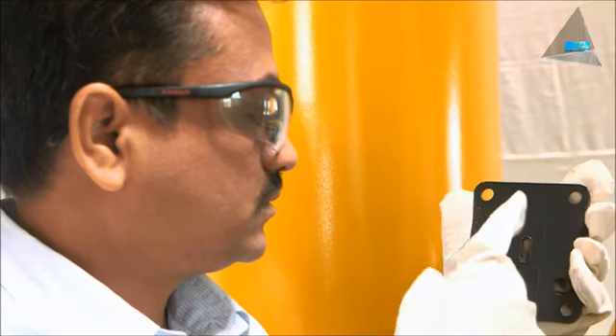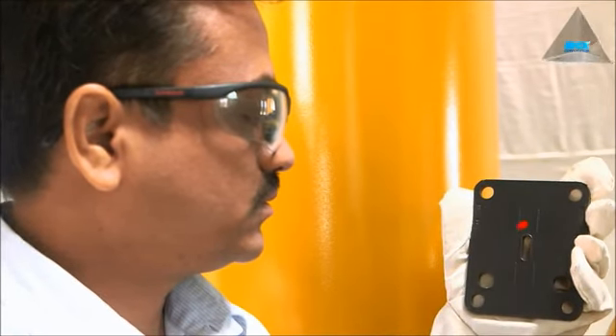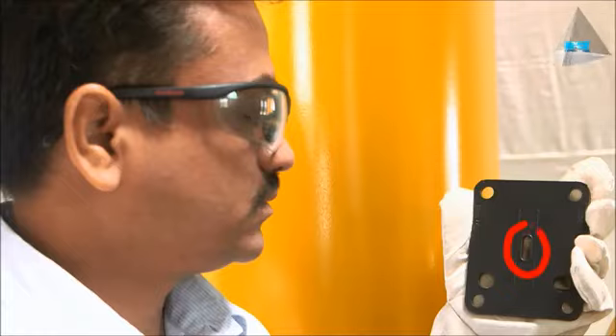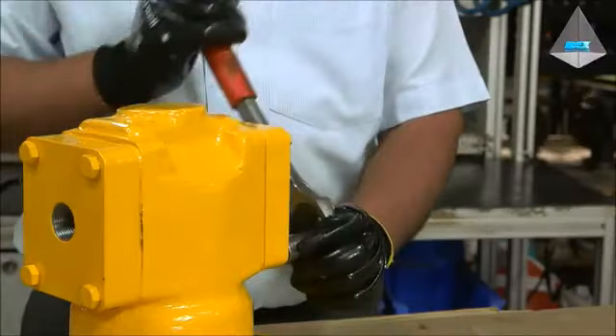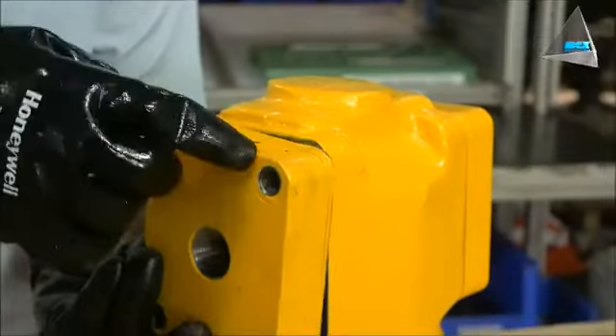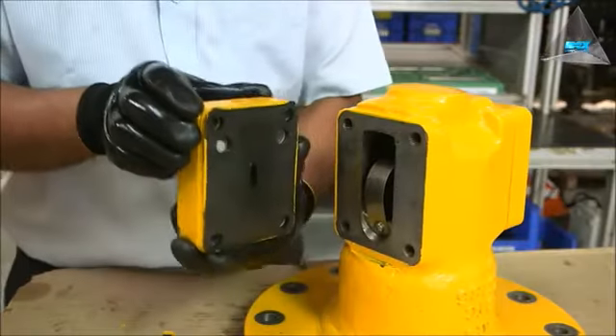Air eliminator maintenance. Foreign particles may get deposited on the valve plate near the vent due to atmospheric dust or with the product. This may cause leakage through the vent. The valve plate can be accessed as per the pictures shown here and would need to be cleaned.